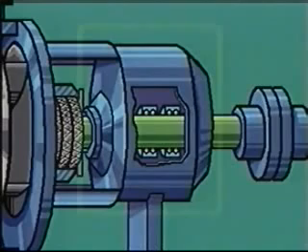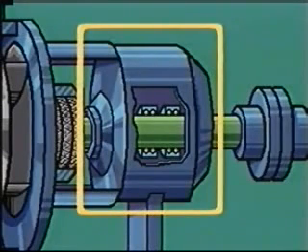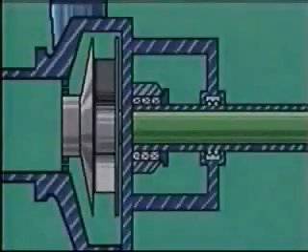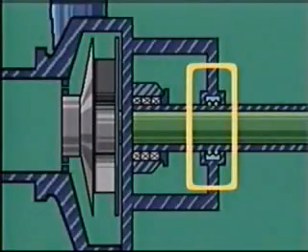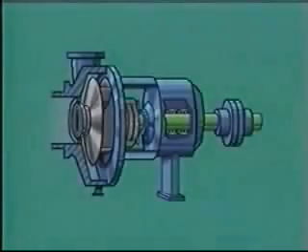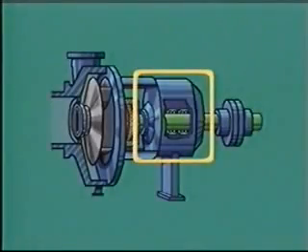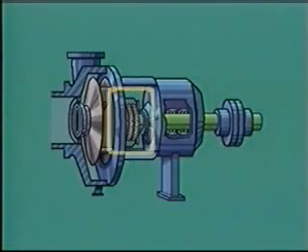Now to bearings. They support the shaft and reduce friction as it rotates in the casing. They do even more. They control the forward and backward movement, the thrust of the shaft, as well as the shaft side-to-side or radial movement. That keeps the shaft from rubbing against the pump casing. Bearings can be here, in the pump casing on small process pumps, or separated in special housings on larger ones. Last, are seals or packing. They're used to stop or cut fluid leakage around the shaft.